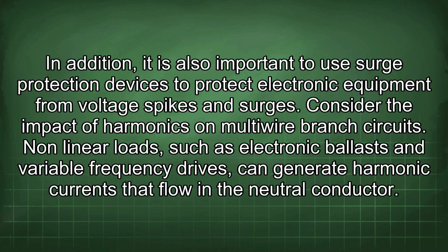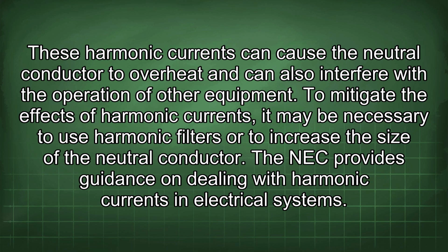Consider the impact of harmonics on multi-wire branch circuits. Nonlinear loads, such as electronic ballasts and variable frequency drives, can generate harmonic currents that flow in the neutral conductor. These harmonic currents can cause the neutral conductor to overheat and can also interfere with the operation of other equipment. To mitigate the effects of harmonic currents, it may be necessary to use harmonic filters or to increase the size of the neutral conductor. The NEC provides guidance on dealing with harmonic currents in electrical systems.